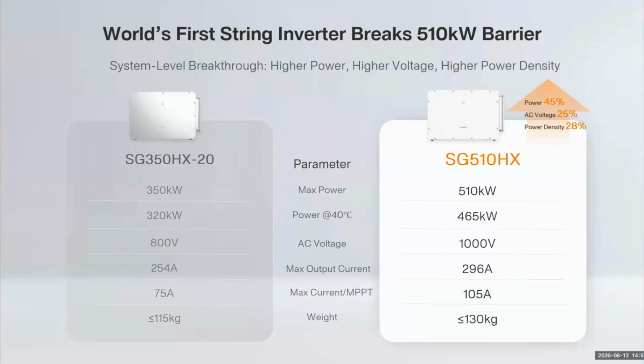So compared with our previous model, the SG350HX, the second generation, our 510 model increased maximum power from around 350 to 510 kilowatts, while AC voltage rises from 800 to 1000 volts. Maximum current per MPPT also increased from 75 to 105 amps. At the same time, the weight remains below 130 kilograms. So overall, we achieve about 45% higher power, 25% higher AC voltage, and 28% higher power density. For EPCs, that means fewer units and installation points. And for owners, I think it creates additional BOS savings.